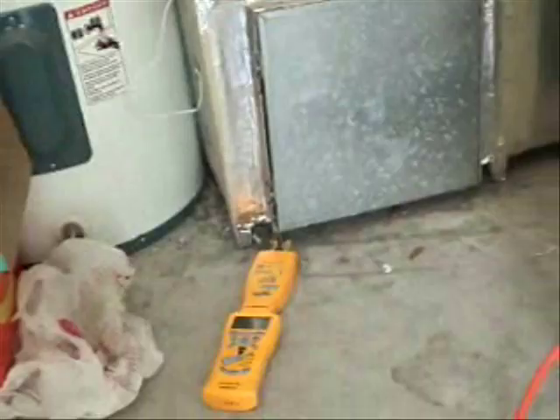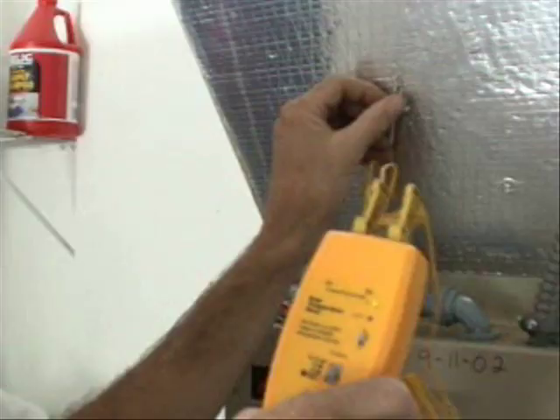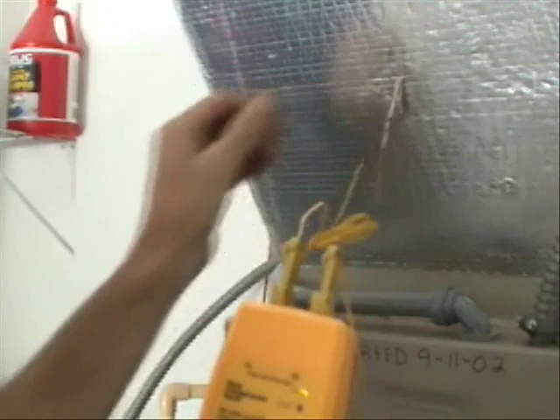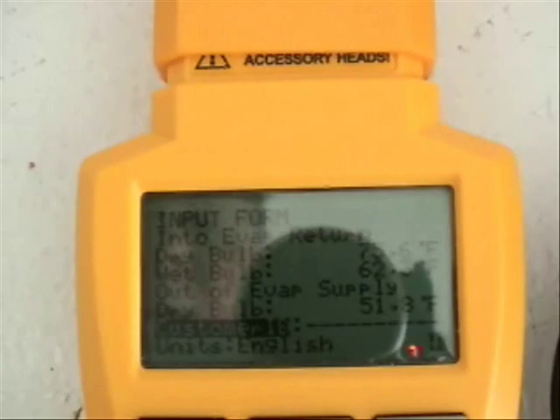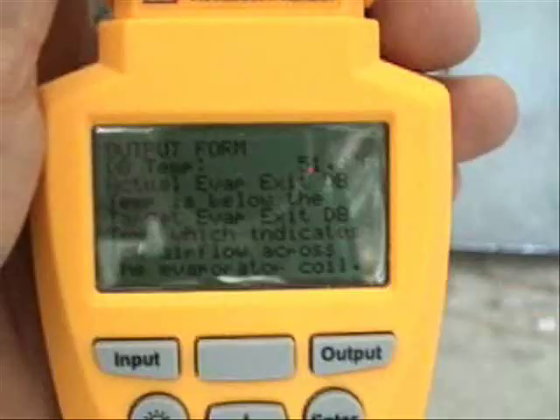It also says to test air flow with the target evaporator exit temperature test. I've placed both my dry bulb and wet bulb thermocouples inside the return at my air handler. I entered a dry bulb reading of 75.6 and a wet bulb of 62.4. I put the dry thermocouple inside the supply end of the evaporator and got a dry bulb reading of 51.3 degrees.